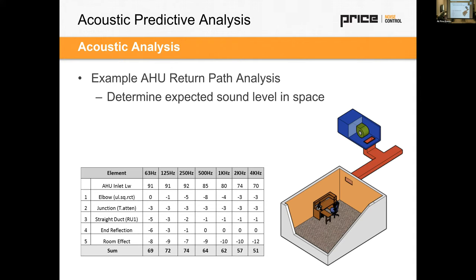I've done this over my career, where you numerically collect the information and then mathematically average and deduct your path from your source. In this case, we have an air handler unit and we have the sound power on the inlet side. You usually need those 8 octave bands to analyze that appropriately. From there, we deduct the sound levels and values depending on the path elements. Traditionally this is done using handbooks, the ASHRAE applications handbook or publications that publish how much sound absorption different things would have. You would then have your room.